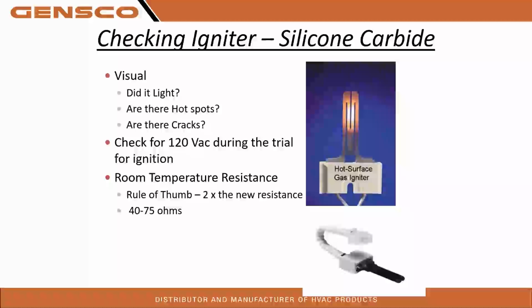So room temperature resistance, rule of thumb, 2 times the new resistance, 40 to 75 ohms is the window. I've had some dealerships say once they go over 100, we offer the homeowner a new one. That's up to the individual shops. But you can see in the slide deck, we have very specific ohm values from the manufacturer that they consider good.